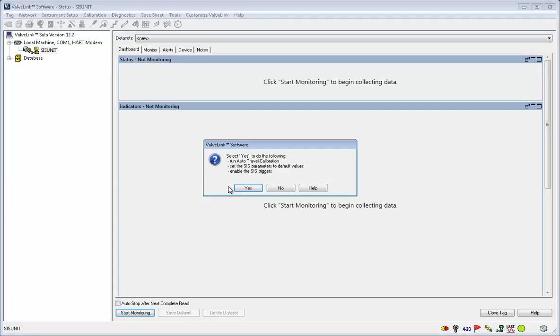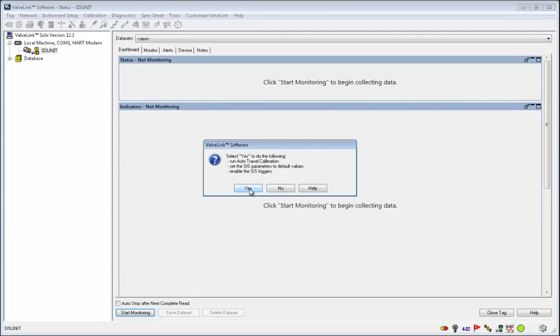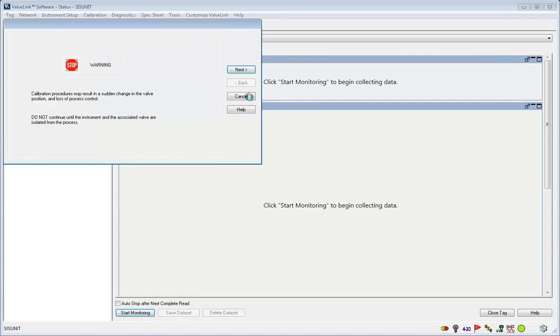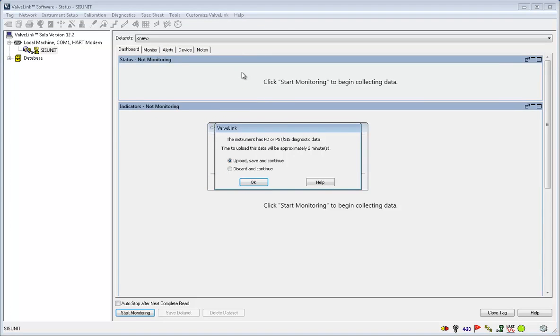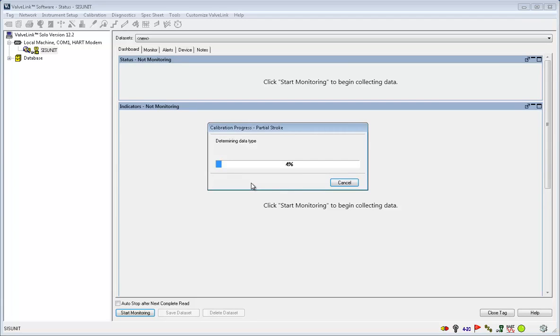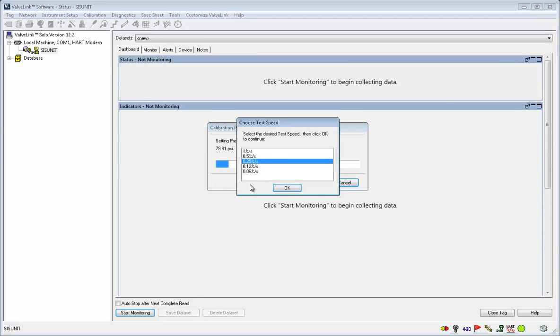You can let ValveLink automatically run the auto travel calibration, set the SIS parameters to default values, and enable the SIS triggers by clicking Yes. This window offers a warning that the valve will move now. Click Next to continue. If your instrument has unsaved diagnostic data, now is your chance to save it. While ValveLink performs a partial stroke test calibration, the test speed window will pop up. Choose a percentage per second and click OK. I'm going to set the test speed to 1% per second.